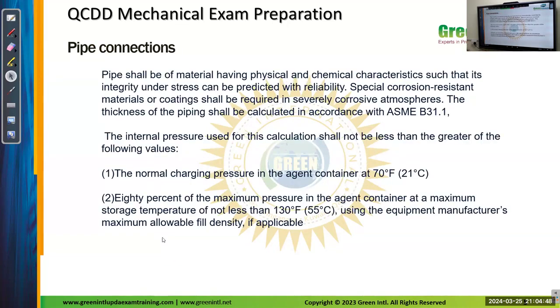So, pipe connections. The main condition of this type of fire extinguishing system is that some of these chemicals are corrosive. So we cannot use metal pipes or cast iron pipes that are corrosive or reacting with these chemicals; it is not allowed. So pipe shall have physical and chemical characteristics such that integrity can be calculated. Special corrosion resistant materials or coatings shall be required in severely corrosive atmospheres.